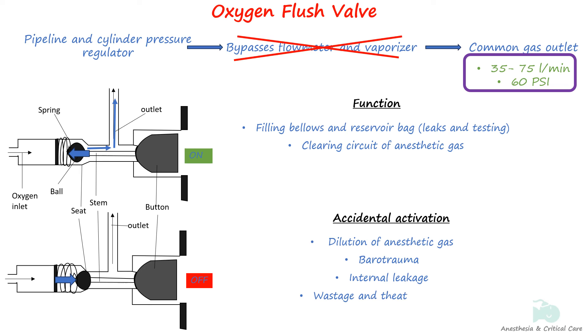However, there are hazards associated with the use of the oxygen flush, such as accidental activation which can cause dilution of anesthetics. The flush button can get stuck in the on position, causing barotrauma to the patient and internal leakage. These can lead to anesthesia awareness, wastage, and pollution of the operating theater.